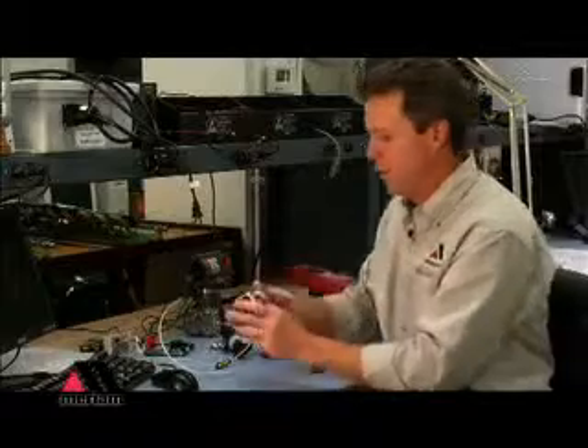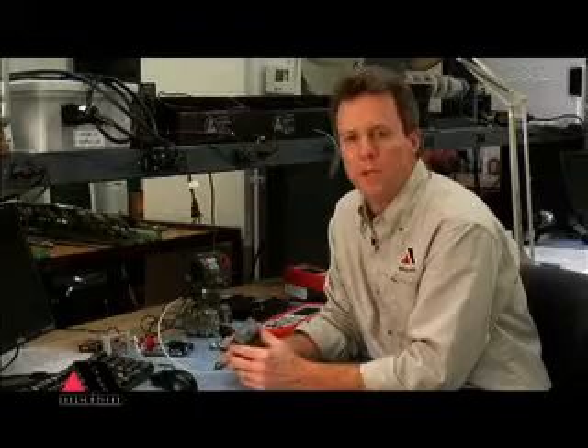We also have temperature modules that are available. These temperature modules will not only measure thermocouple or RTD output, they will also simulate the output of an RTD or a thermocouple. This lets you calibrate transmitters in the field. It allows you to check receiving devices that might be in your 2-wire loops. Our thermocouple module handles up to 12 different types of thermocouples. You can also program it to output in millivolts directly if you'd like to do that.